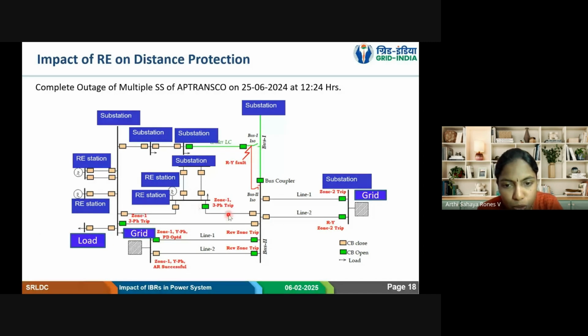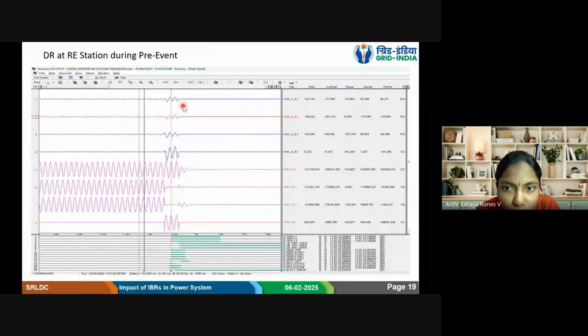Because of that, these two major evacuating lines were lost. So all the RE connected to that particular grid also got lost. So there was a complete outage. So this is a real-time case. When we looked into the DR, this is the kind of signature. Actually, the fault was an RY fault, but this is what we observe. It will not contribute, this is actually the pre-event. So if you see the pre-event, these are the currents and these are the voltages. Currents were like 122 amps in all the phases, and voltage 127, in a 220 kV system.